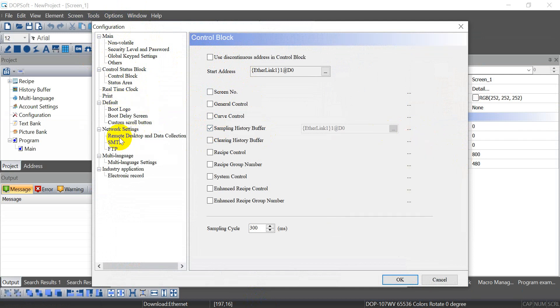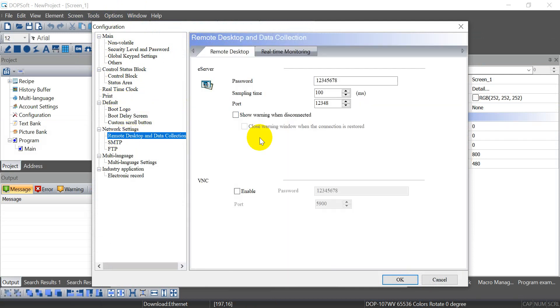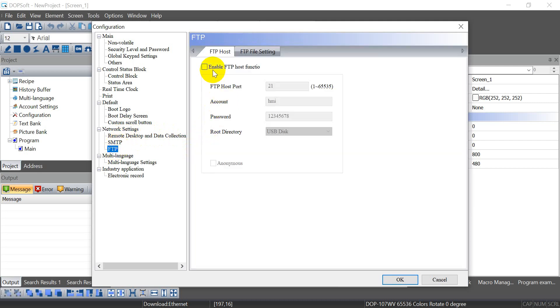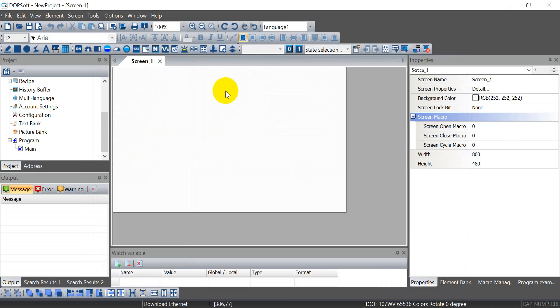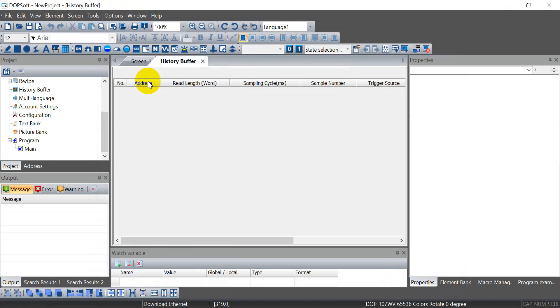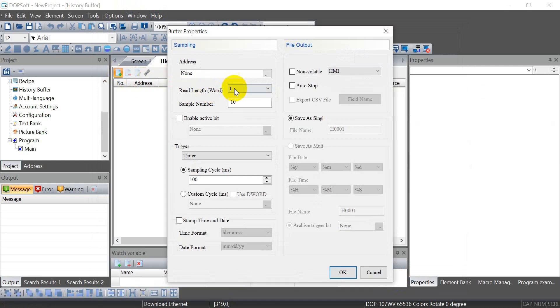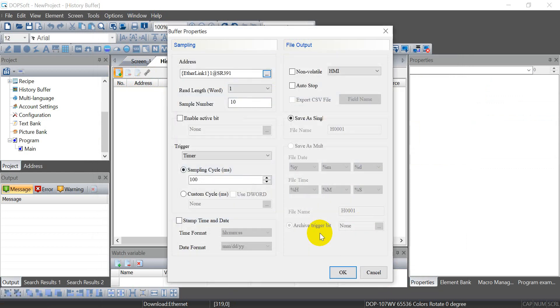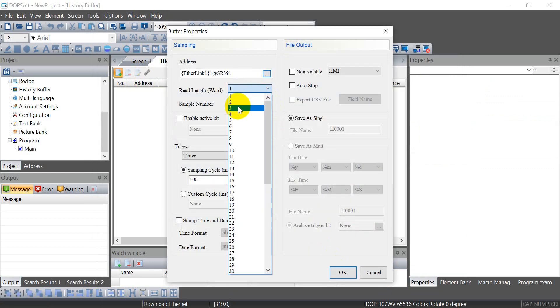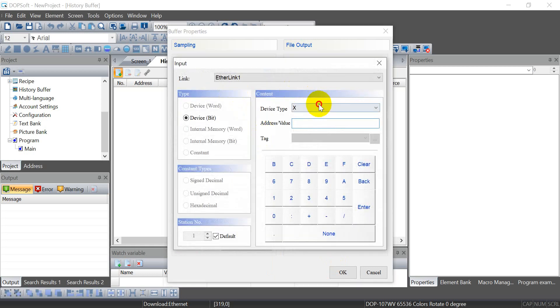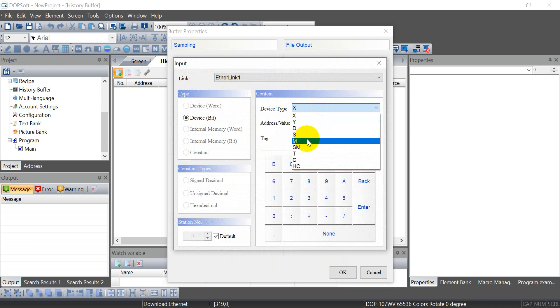Then we have to enable VNC function and also FTP function. After that, let's go to history buffer setup. Again, here we assign to special register 391, 7 words and 1000. Then the enable bit we use M0.